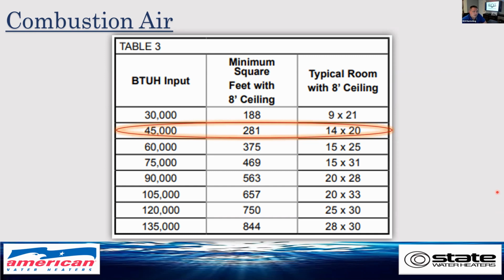So let's look at a typical 40 to 50 gallon unit. With an 8-foot ceiling, you would need a room size of 14 by 20. How many mechanical rooms are that big nowadays? And keep in mind, you have to deduct the space that the furnace, boxes, or a laundry washing machine and dryer would consume.